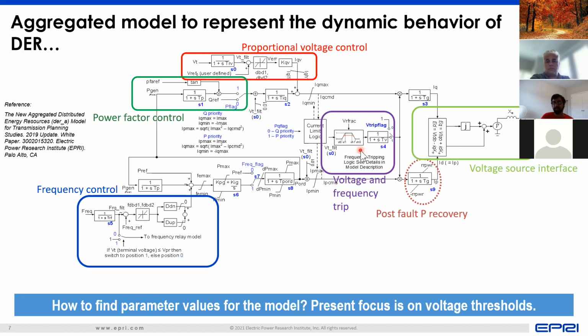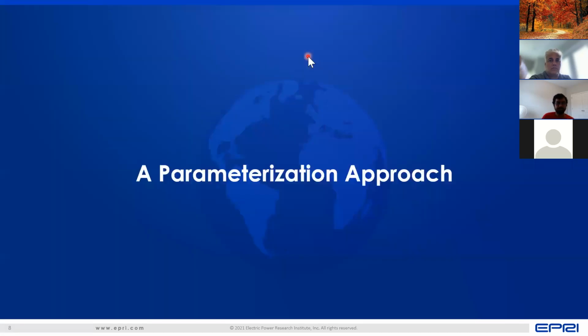So remember the tripping diagram which I showed on the first slide, where you have that nonlinear trip coming about with different levels of voltage. That is the behavior that is represented by most of the DER on the feeder today. So the aim is to first try to parameterize this trip logic within this aggregated model so that transmission planners can start getting visibility into some of those trippings that can occur. That doesn't mean to say that things like voltage control, proportional voltage control, or frequency control are not important and don't need to be parameterized. It's just the priority in which we are addressing this parameterization challenge.